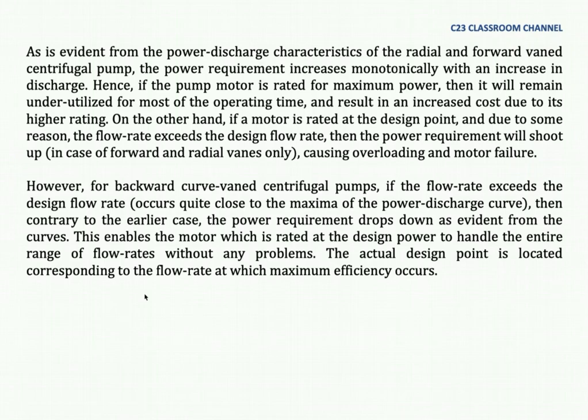As is evident from the power-discharge characteristics of radial and forward vane centrifugal pump, the power requirement increases monotonically with an increase in discharge. If the pump motor is rated for maximum power, it will remain underutilized for most of the operating time and result in increased cost. On the other hand, if a motor is rated at the design point and the flow rate exceeds the design flow rate, the power requirement will shoot up in case of forward and radial vanes, causing overloading and motor failure. However, for backward curve-vaned centrifugal pumps, if the flow rate exceeds the design flow rate close to the maximum of the power-discharge curve, the power requirement drops down. This enables the motor to handle the entire range of flow rates without problems. The actual design point is located corresponding to the flow rate at which maximum efficiency occurs.